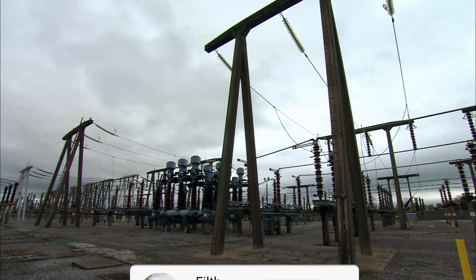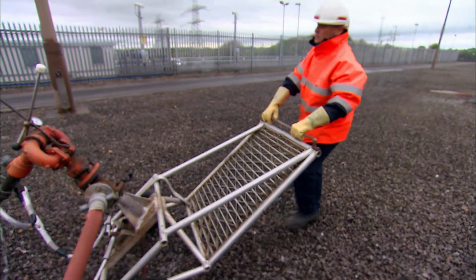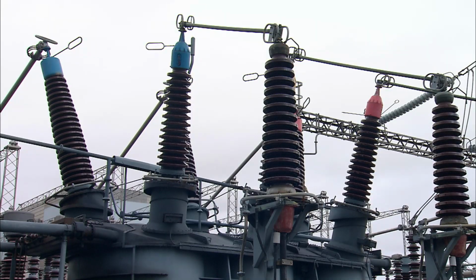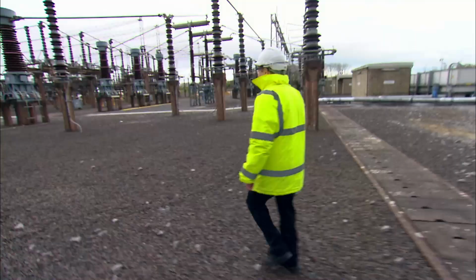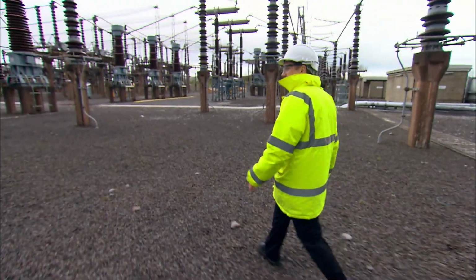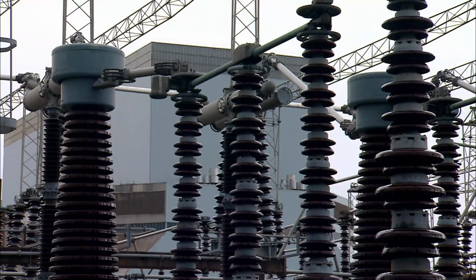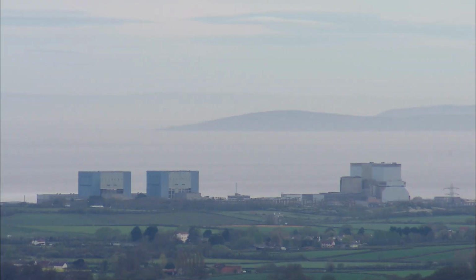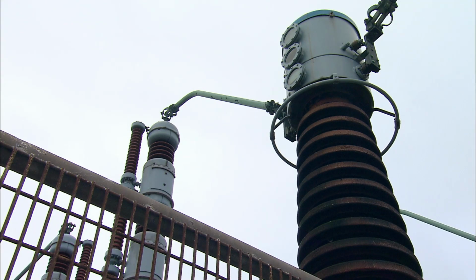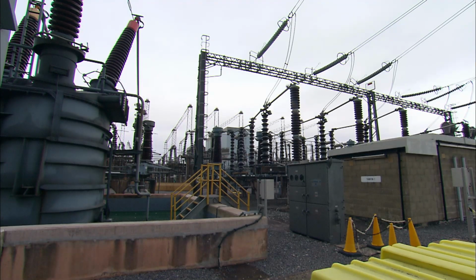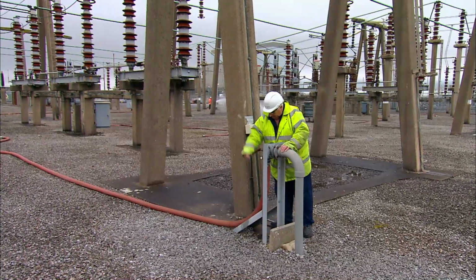At Hinkley Point nuclear power station on the banks of the Bristol Channel, the cleaning team is about to mix salt, water, and an awful lot of electricity. They're cleaning the live 275,000 volt substation that connects the power station to the grid. Salt blown from the sea lets the electricity flash over to the ground. If that happens, the substation shuts down. The invisible layer of salt has to be washed off.